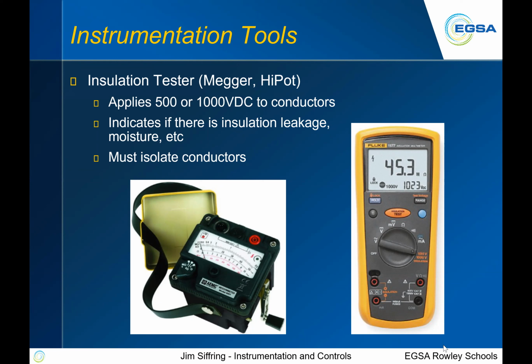Much more common in high humidity areas, where the insulation in a generator end will collect moisture and start to have insulation leakage. It may be a very, very little bit, but over time that insulation starts breaking down and then you'll end up with an arc internally in that generator end. So if you can discover that, and really what it comes down to is you're going to chart these values. You'll find out what your insulation leakage is and then chart it over time. And that'll give you an idea if you need to have the generator cleaned up, baked, or heated up to get the moisture out of it, anything like that.